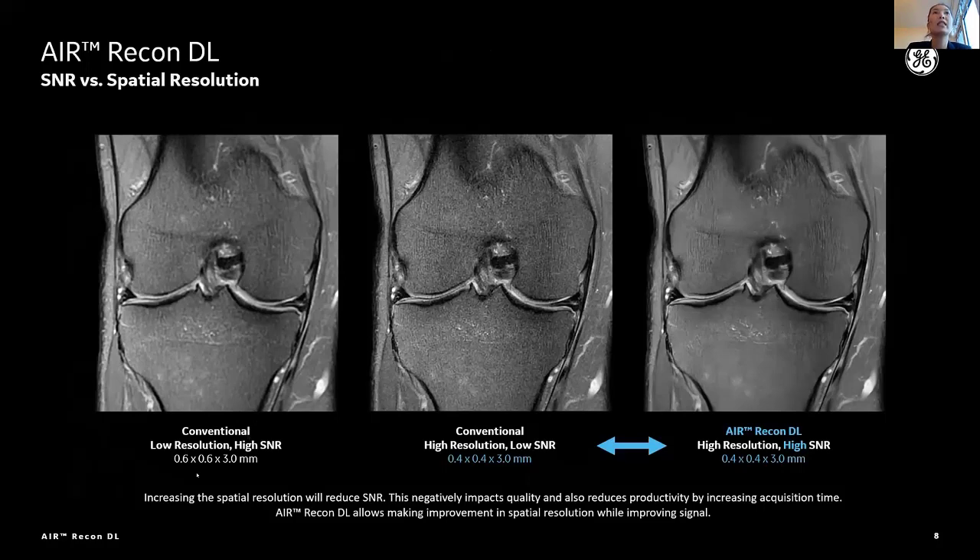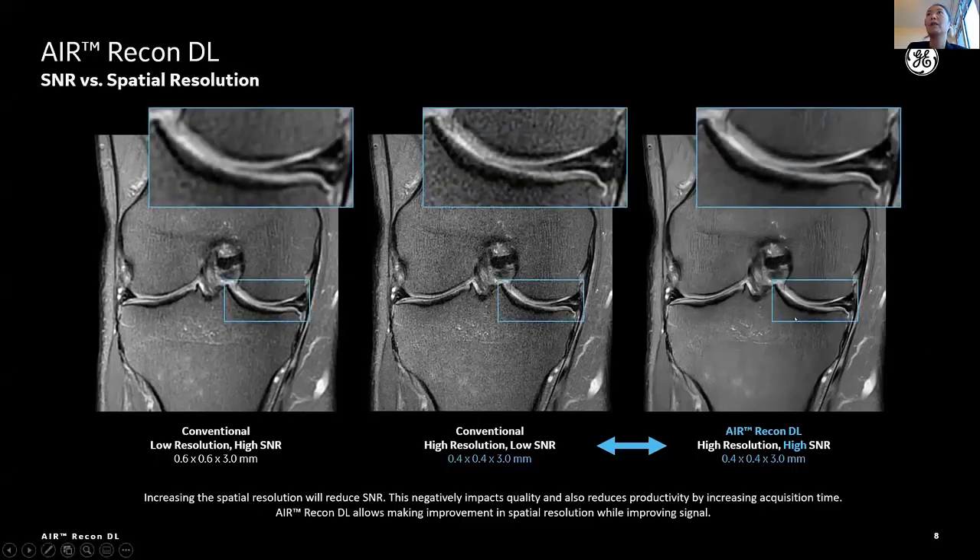The left knee image has 0.6 x 0.6 spatial resolution with 3 millimeter slice thickness. If you would like to improve resolution in the same scan time — in this example, 0.4 x 0.4 spatial resolution with the same 3 millimeter slice thickness in the middle — the image gets noisier because we sample less signal in each raw data. But AIR Recon DL boosts up SNR because it can significantly reduce noise. The right image by AIR Recon DL has higher resolution, but you can see higher SNR even compared with lower resolution images. You can see clearer joint visualization on AIR Recon DL images.